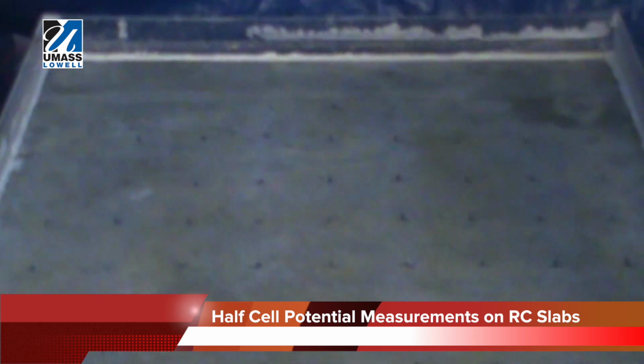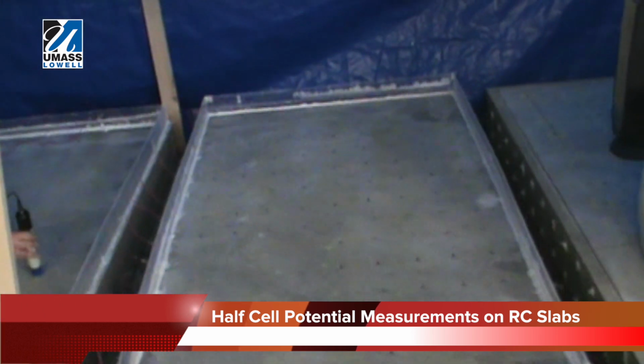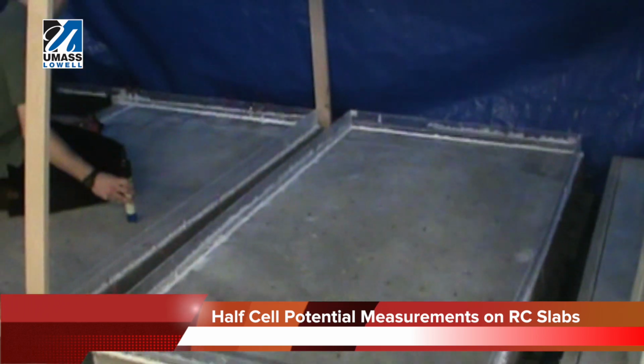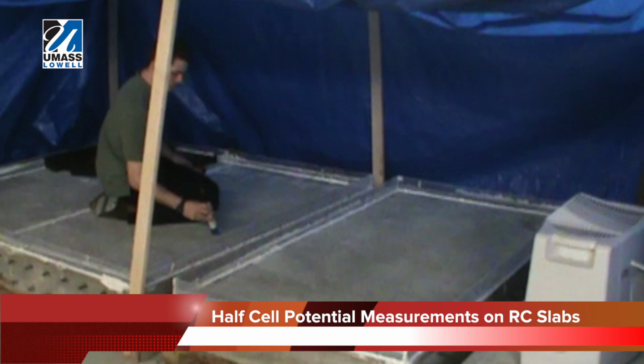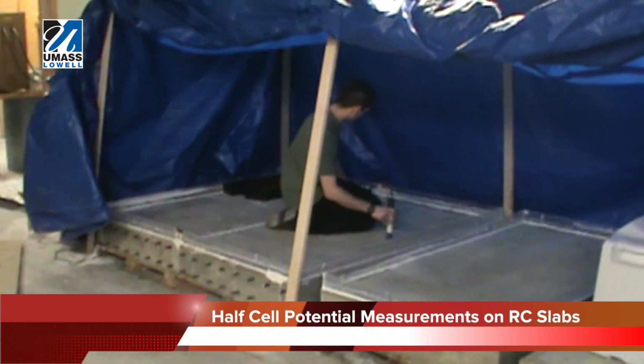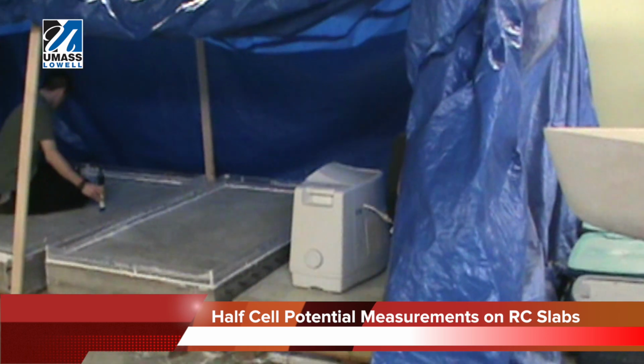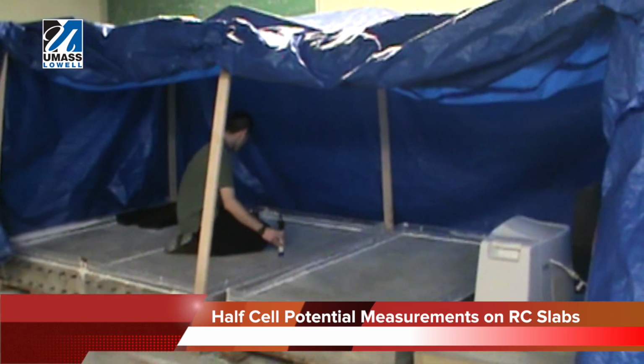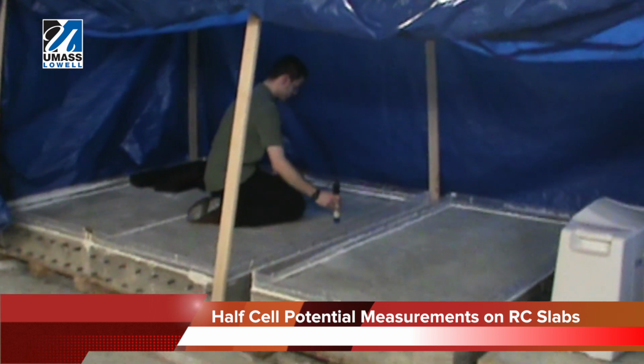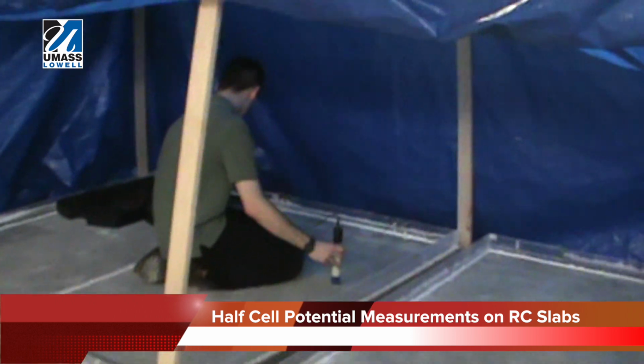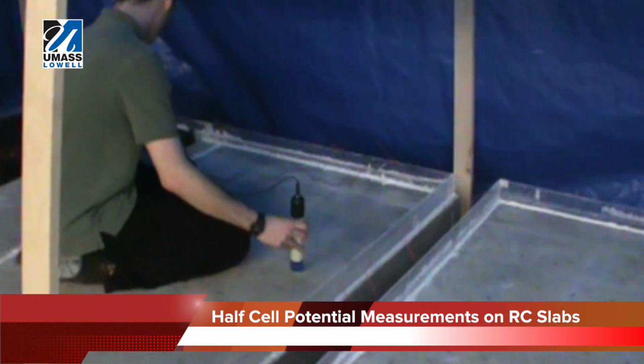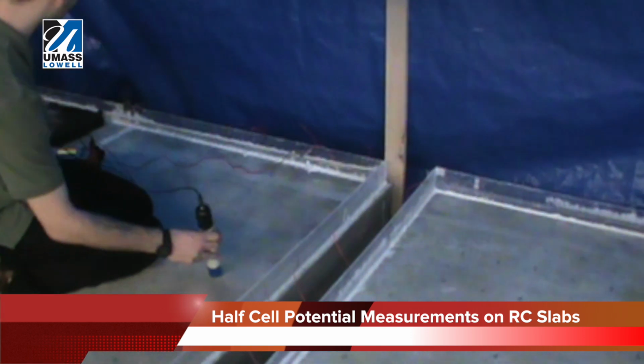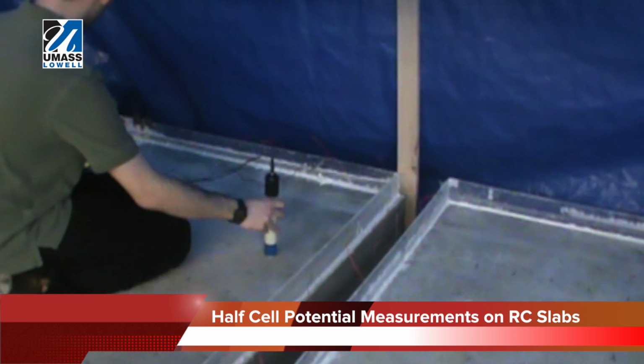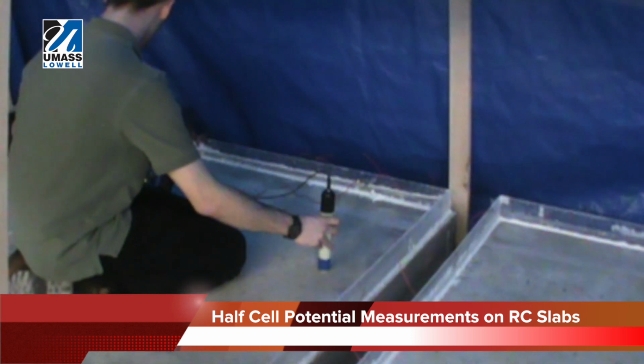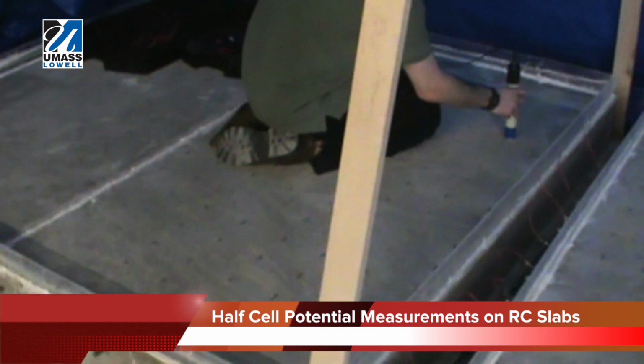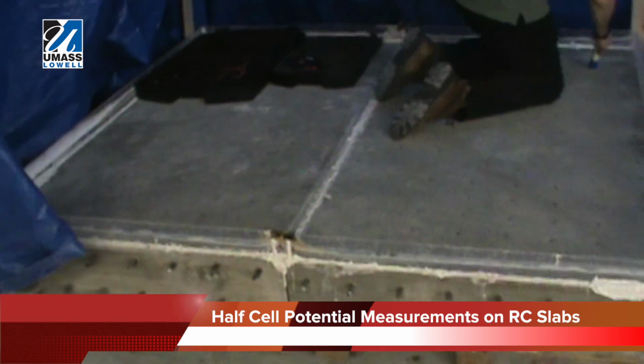One note to keep is that in this video we are using a silver chloride reference electrode. The ASTM C876 standard requires us to use a copper sulfate reference electrode. However, we had some issues with the copper sulfate reference electrode, which essentially made us use the silver chloride reference electrode. This should not be an issue because all we have to do is transfer the potential from the silver chloride reference electrode to the copper sulfate reference electrode potentials, and we should be able to achieve the same reading as the ASTM C876 standard.